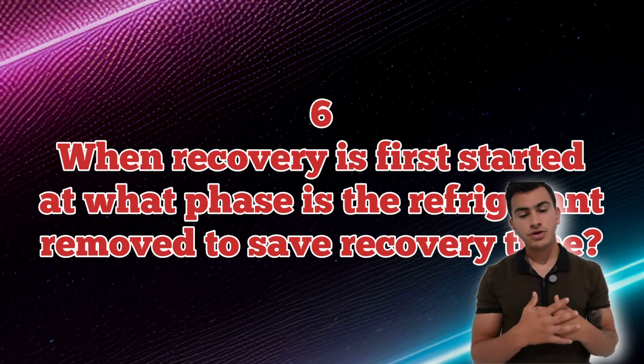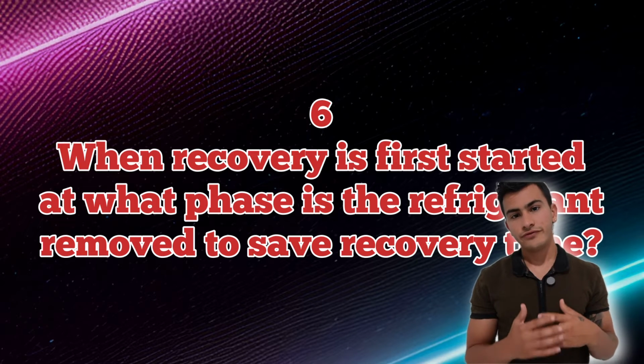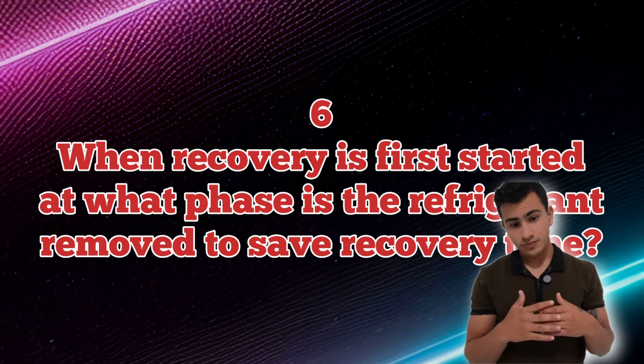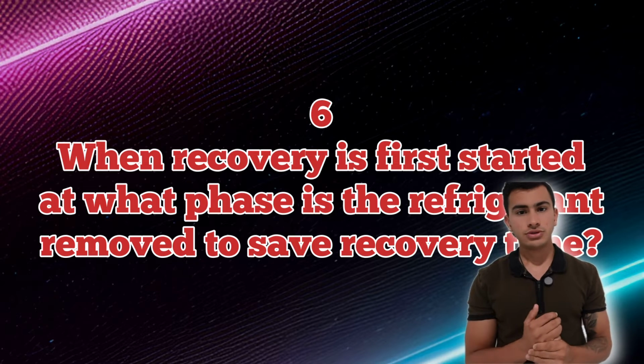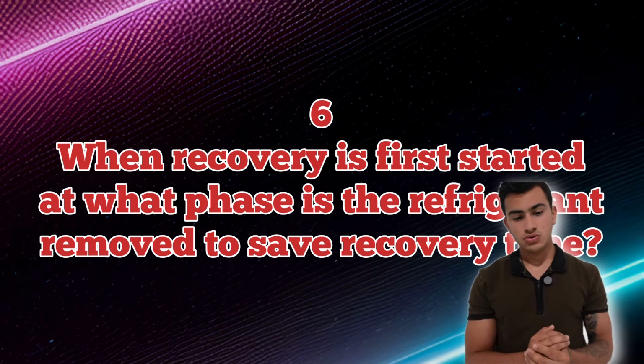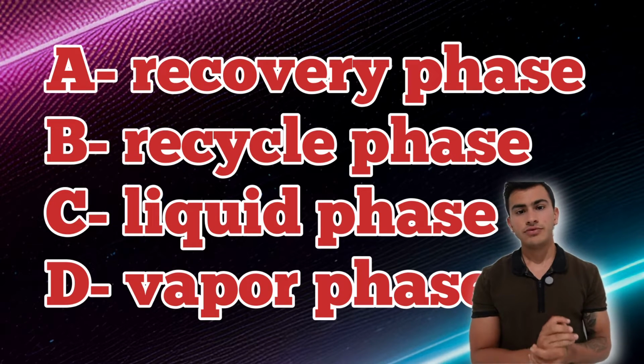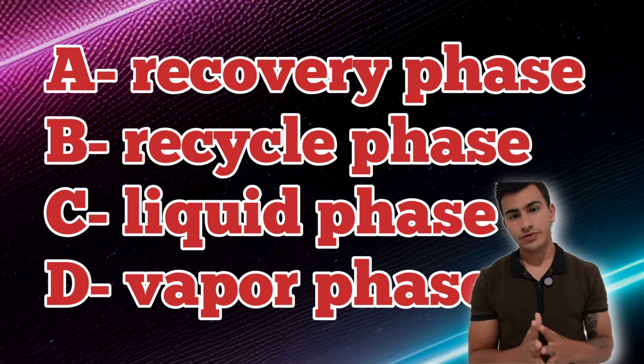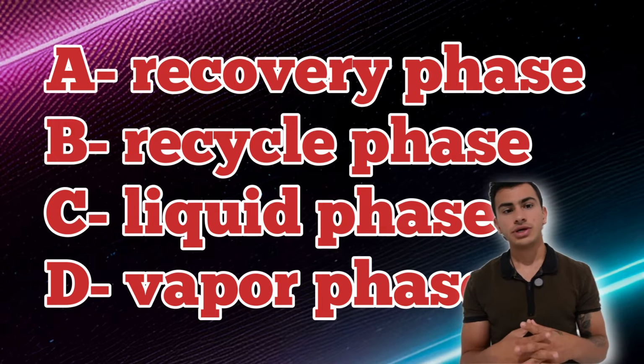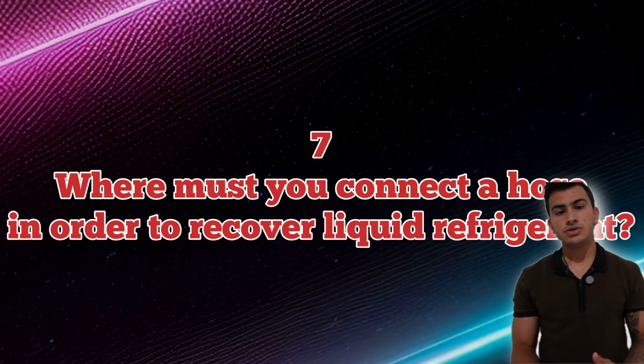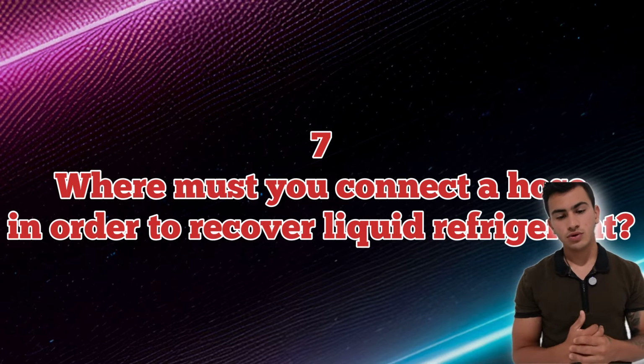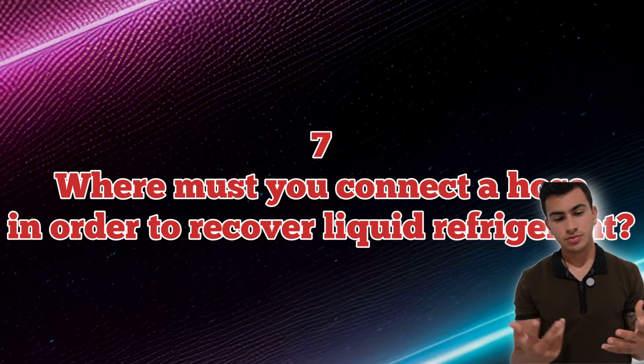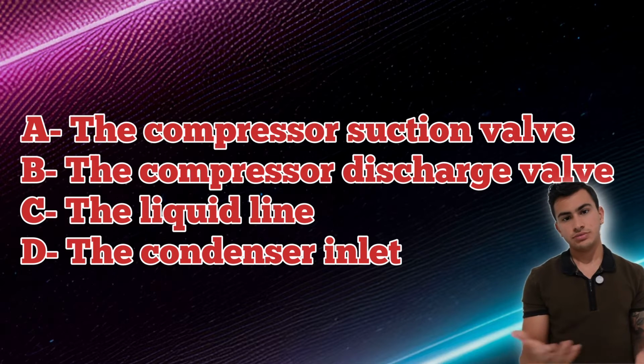So when recovery is first started, at what phase do you want to recover the refrigerant to save time? So you always want to recover refrigerant as a liquid phase, and that would save you time. So for this question, where must you connect the hose in order to recover liquid refrigerant? It's kind of simple.